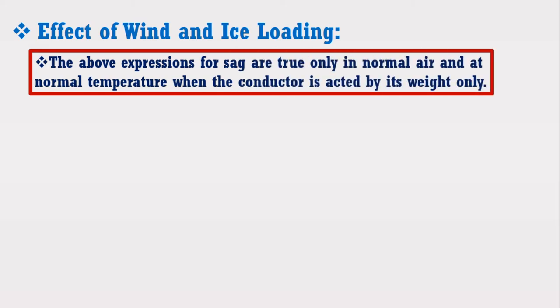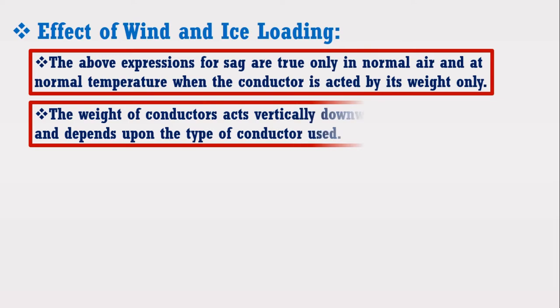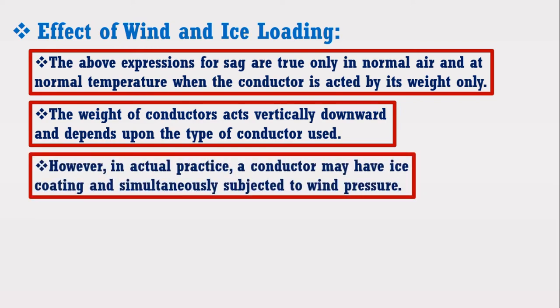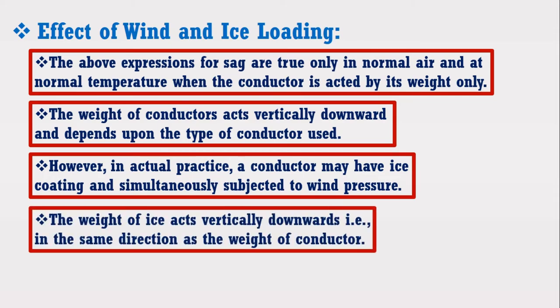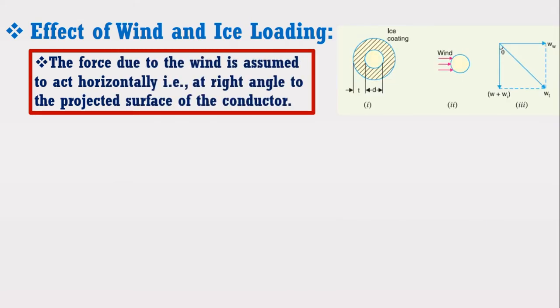Now I am going to discuss the effect of ice and wind on the sag. The above expressions for sag are true only under normal air and temperature when the conductor is acted upon by its weight only. The weight of the conductor acts vertically downward. However, in actual practice, a conductor may have ice coating and simultaneously be subjected to wind pressure. The weight of ice acts vertically downward in the same direction as the conductor weight. The force due to wind pressure is assumed to act horizontally at right angles to the projected surface of the conductor, as shown in the figure.